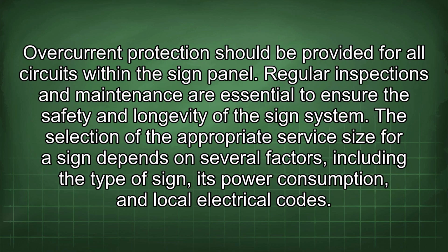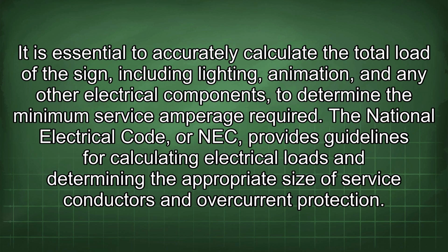Overcurrent protection should be provided for all circuits within the sign panel. Regular inspections and maintenance are essential to ensure the safety and longevity of the sign system. The selection of the appropriate service size for a sign depends on several factors, including the type of sign, its power consumption, and local electrical codes. It is essential to accurately calculate the total load of the sign, including lighting, animation, and any other electrical components, to determine the minimum service amperage required.